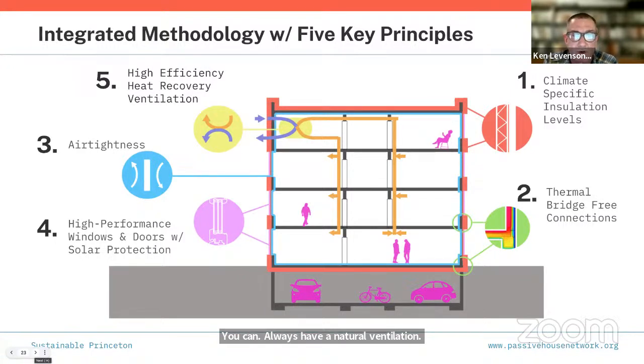So we're providing ventilation like all buildings do, but rather than an intermittent bath fan or kitchen fan pulling air through the cracks in the building enclosure willy-nilly, we are with intention supplying fresh air 24/7 to the served spaces - living rooms, bedrooms, offices, classrooms - and exhausting 24/7 from the service spaces - bathrooms, kitchens, hallways, utility rooms, and such.